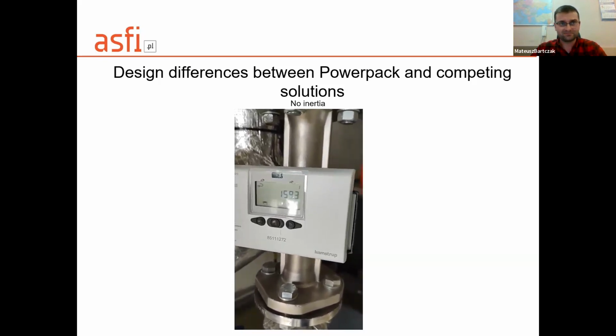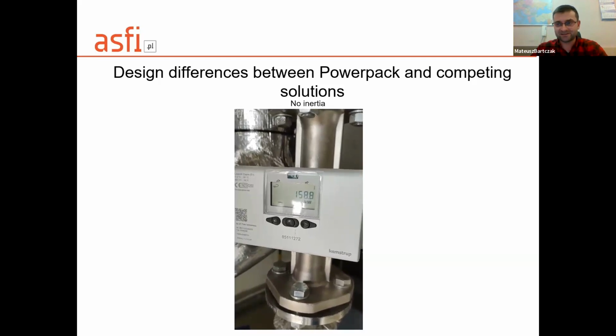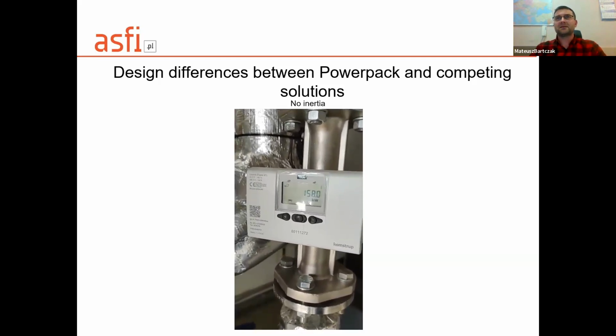Attention, you can write down the greatest secret of heat recovery. The most important thing is to maintain full oil flow through the heat exchanger. If you can control the temperature of the oil on the exhaust of the heat exchanger, you have no inertia on this valve near the radiator. You can get as much heat as is currently available at this moment. Your compressor will work well.